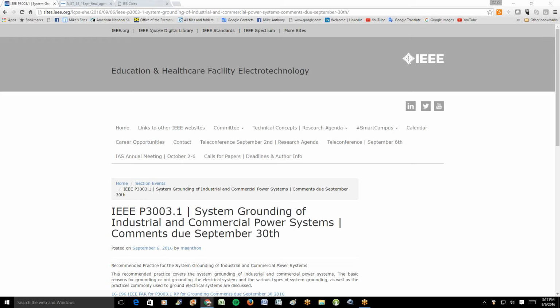We were talking a bit about the feasibility, the imperatives, the drive to use system grounding of campus power systems to reduce fault current. That's important when you're wiring up one or two substations at 13.2 kilovolts and you've got guys working on it. You can limit your fault current down to about, well, actually you can scale it according to any fault level you want, though you'll find variations in that because of the length of the feeders and the cable types, et cetera, et cetera.